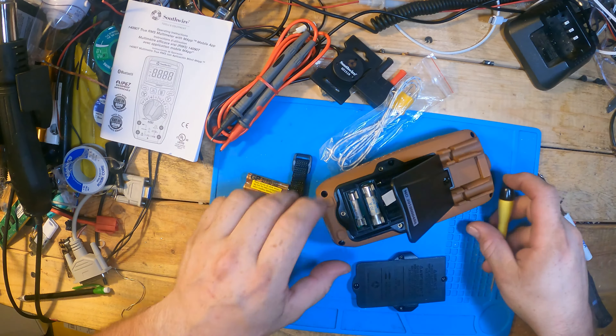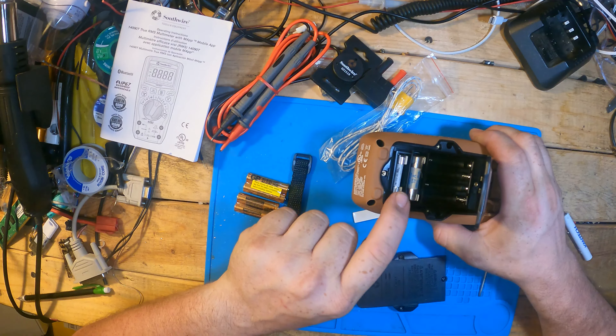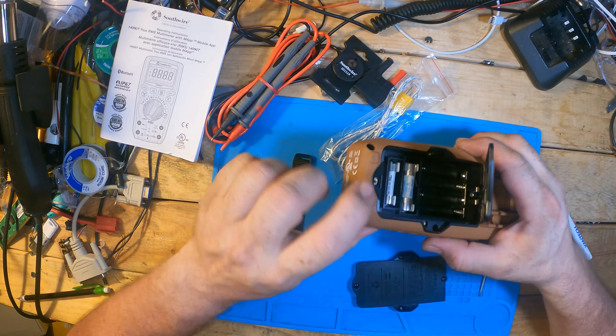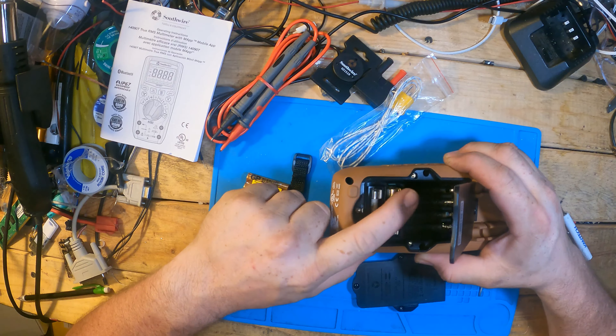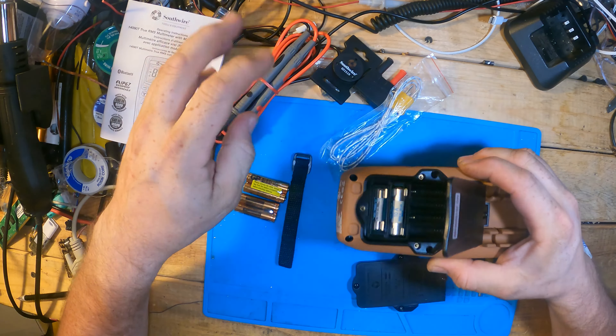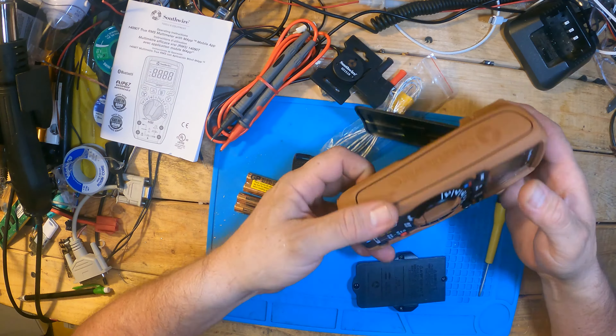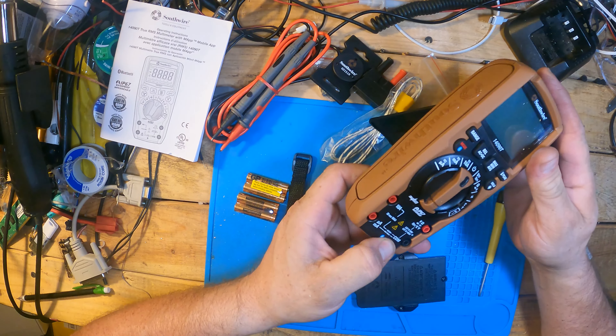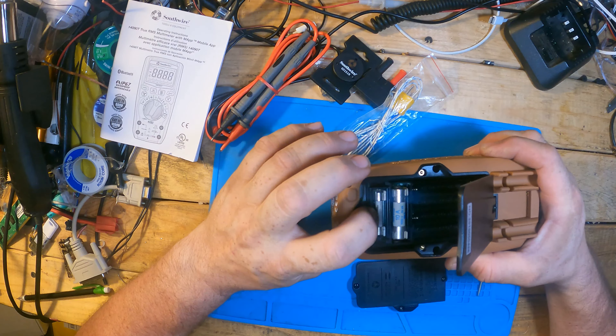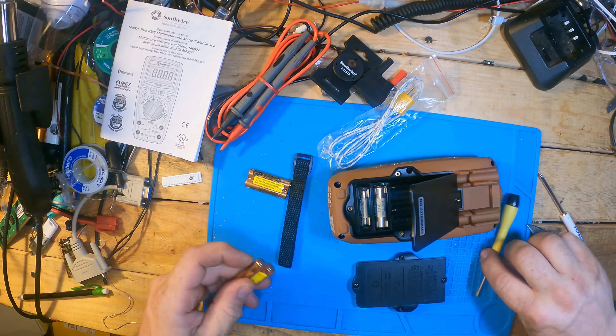If you pry up on the front and the back — okay, this is nice. This is where I had problems. You had to take the whole meter apart — the whole clamshell — to replace these fuses on my old one. These are your amperage fuses. If you accidentally overload 10 amps, or 800 milliamps on this one — 500 on my old one — it would pop these fuses. They are kind of expensive, but not terrible considering the price of the meter. It's well worth it.